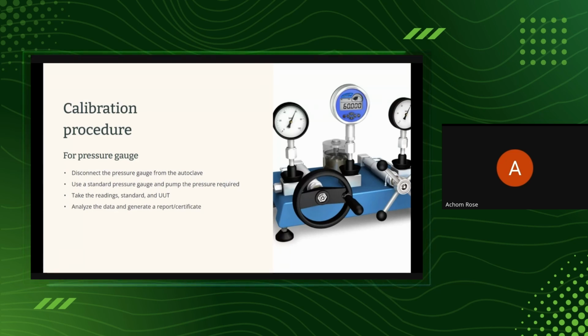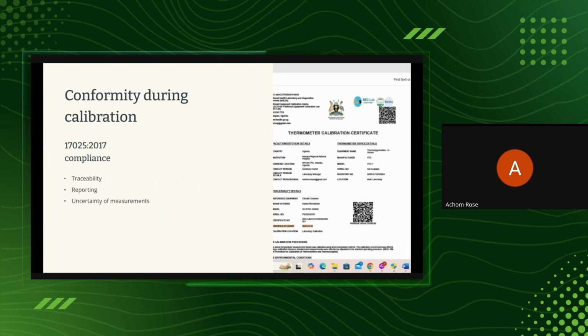Okay, so basically, after we have done all this, like I said, we need to have conformity. You have to be sure that whatever data that you're producing conforms to the 17025. So what are the key things that the 17025 highlights? It has so many things, but the key thing when you're doing calibration, one is traceability. And when we talk of the word traceability, metrological traceability, you're looking at your measurements being linked to the SI unit of measurement. For example, if you're doing mass, you're supposed to be linking to the SI unit of mass, which is a kilogram. If you're doing temperature, we are going to link ourselves to the Kelvin.